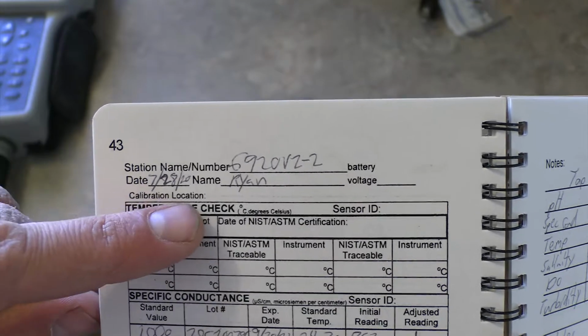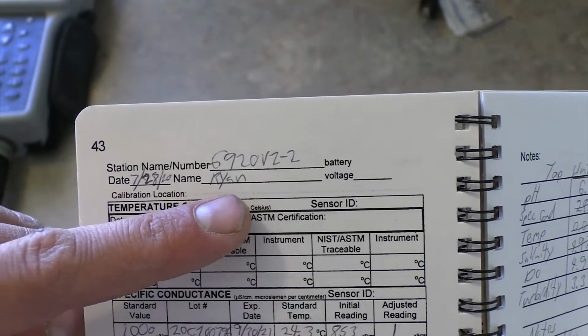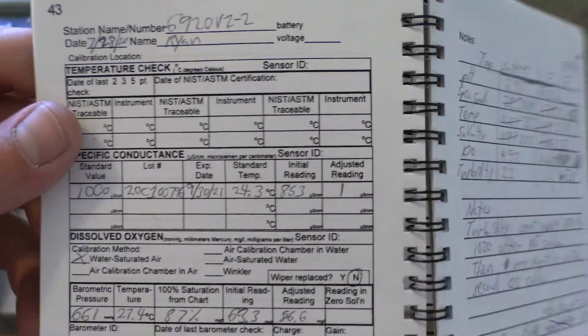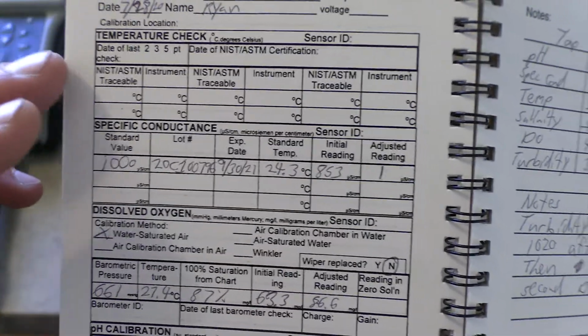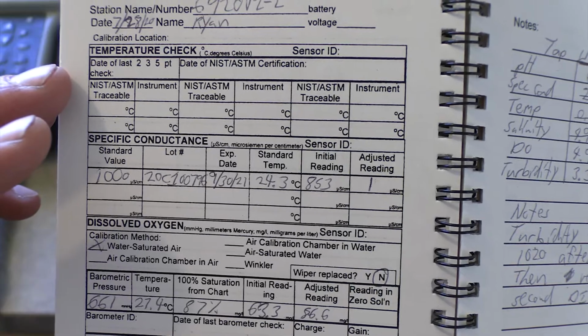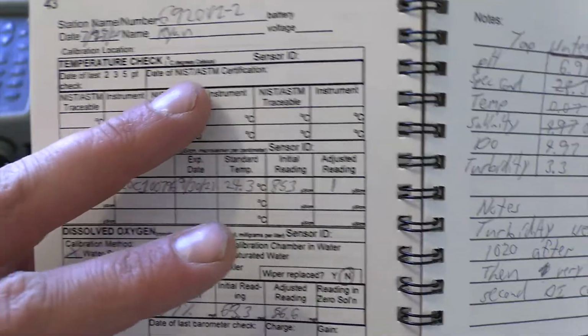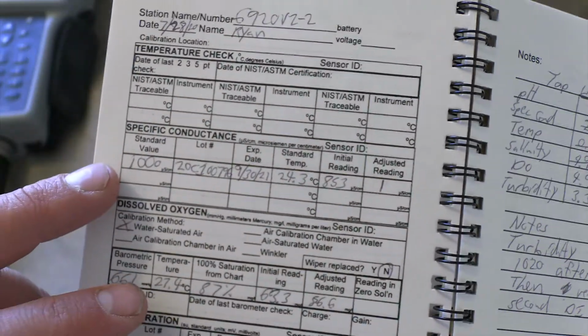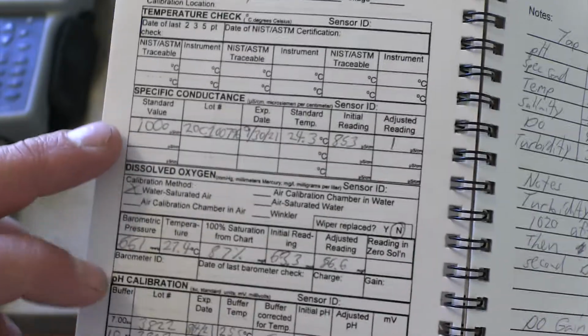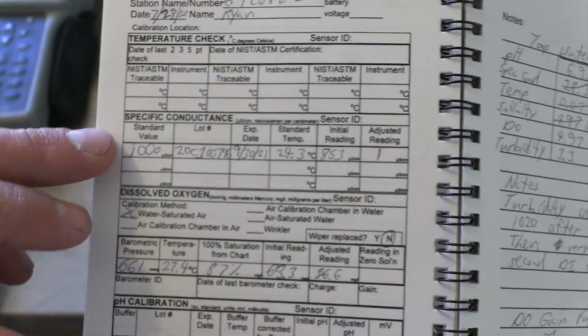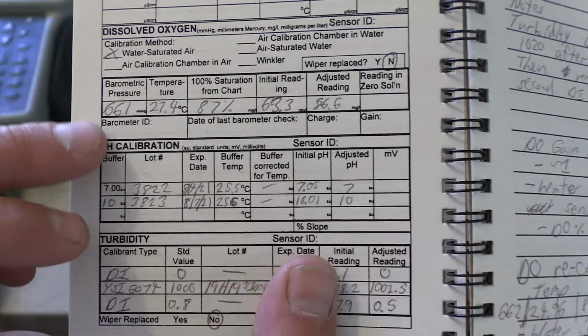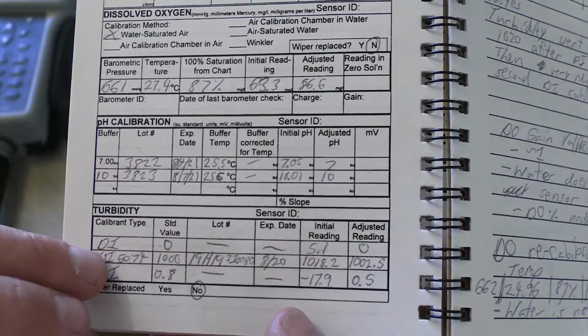I put in the date and my name, and then the major sections we're going to be using here. I was not using temperature. We can use temperature, but we have to have a NIST certified thermometer, and that can be done once a year. The main ones we're going to be doing are specific conductivity, dissolved oxygen, pH, and turbidity.